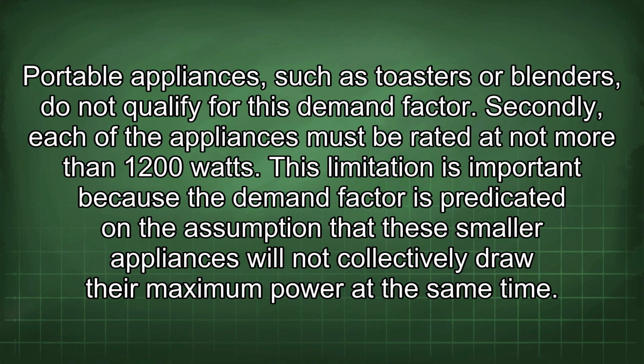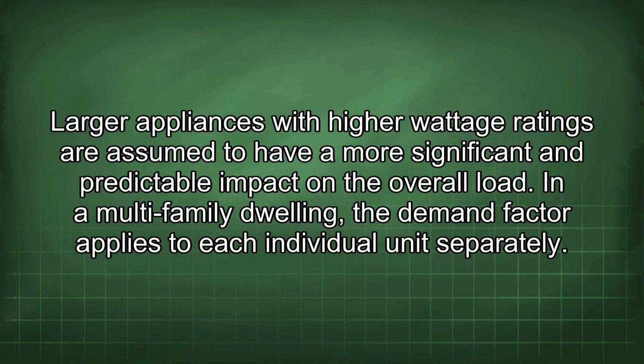Secondly, each of the appliances must be rated at not more than 1200 watts. This limitation is important because the demand factor is predicated on the assumption that these smaller appliances will not collectively draw their maximum power at the same time. Larger appliances with higher wattage ratings are assumed to have a more significant and predictable impact on the overall load.